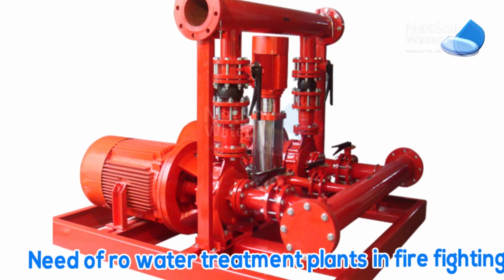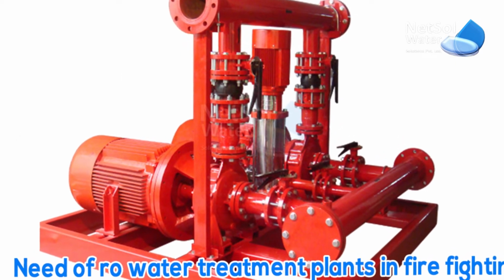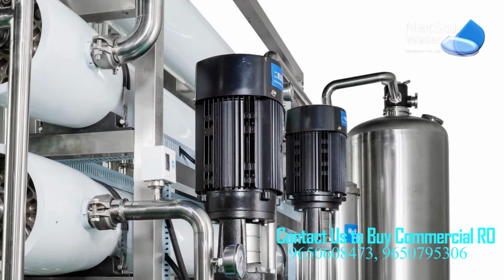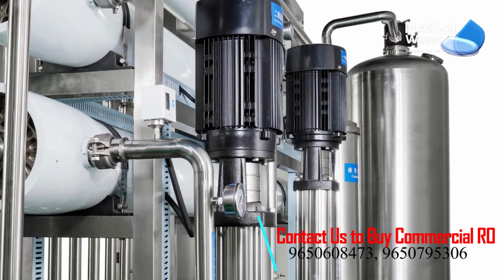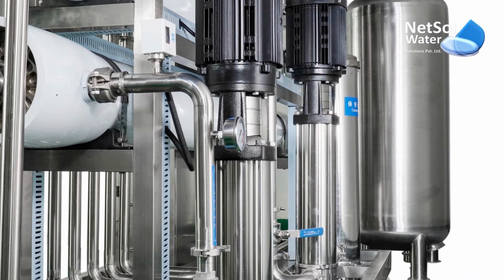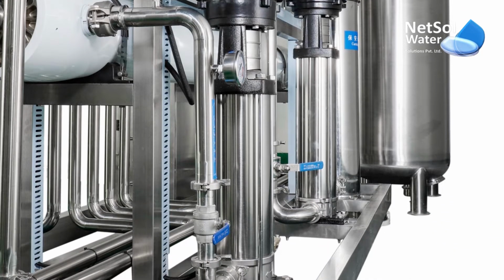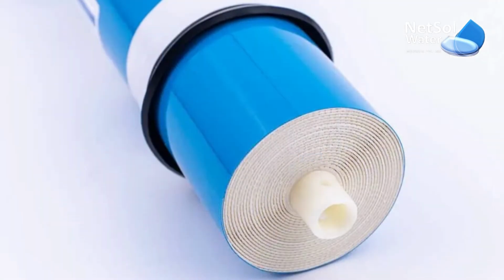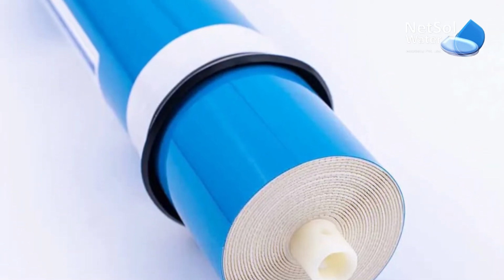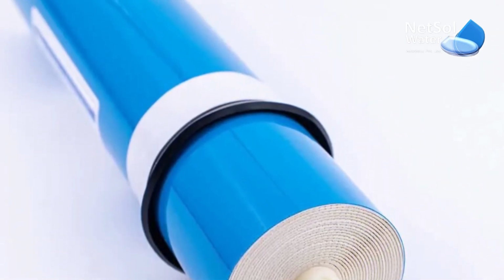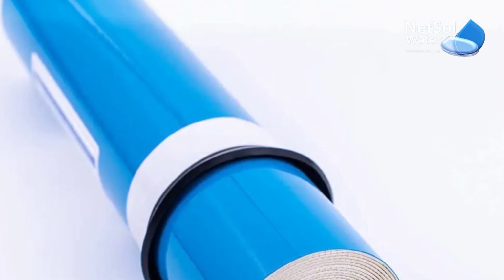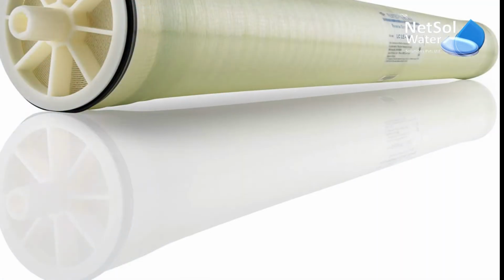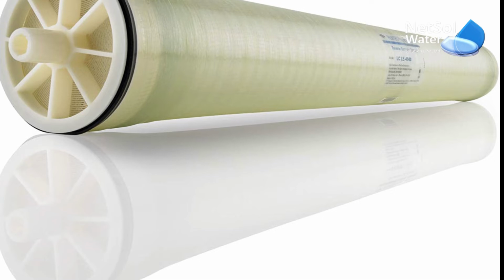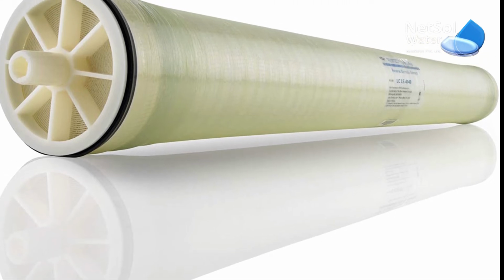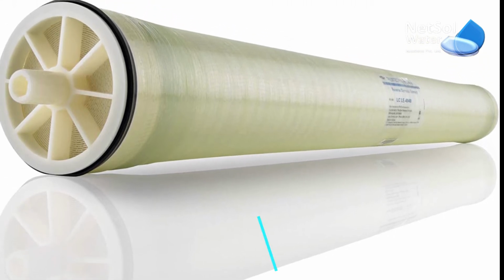Third is to make sure your feed pumps and piping are properly sized. Fourth is to install a CIP or clean in place and disinfection rig for the RO membranes periodic maintenance. Fifth is to use TFC or thin film composite membranes which will deliver high flow while consuming less energy. And sixth is a consistent supply of softened feed water which will aid in the prevention of RO membrane scaling.